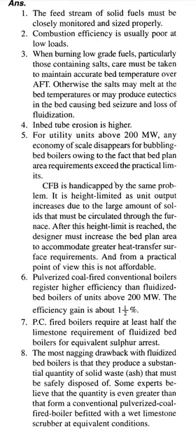When burning low-grade fuels, particularly those containing salts, care must be taken to maintain accurate bed temperature over AFT. Otherwise, the salts may melt at the bed temperatures or may produce eutectics in the bed, causing bed seizure and loss of fluidization. In-bed tube erosion is higher.